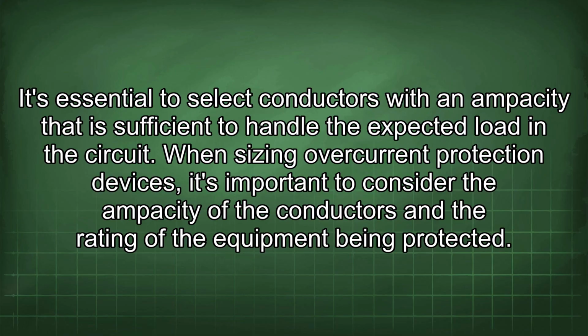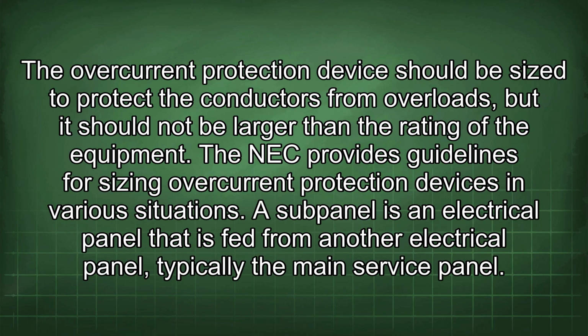When sizing overcurrent protection devices, it's important to consider the ampacity of the conductors and the rating of the equipment being protected. The overcurrent protection device should be sized to protect the conductors from overloads, but it should not be larger than the rating of the equipment. The NEC provides guidelines for sizing overcurrent protection devices in various situations.